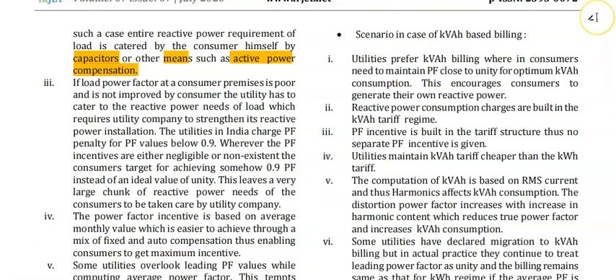That's the thing. In the kVAh billing scenario, the utility prefers kVAh billing wherein the consumer needs to maintain the power factor close to unity for optimum kVAh consumption. This encourages the consumer to generate their own reactive power. Okay. Like if we use more reactive power locally, then our kVAh is well maintained. If capacitive power is more, then it will balance the inductive power. Then the kVA is improved and our consumption will be less.